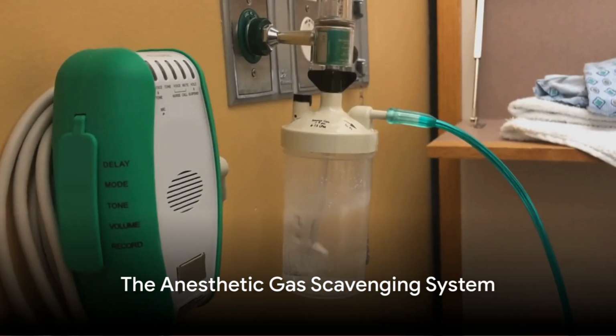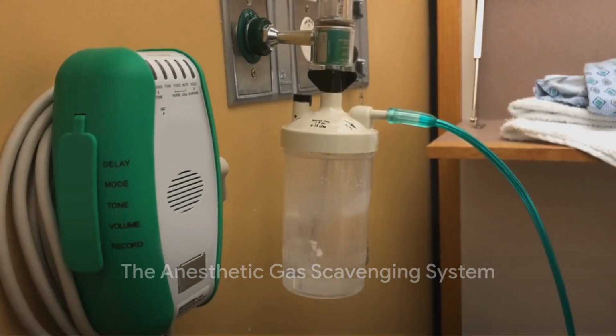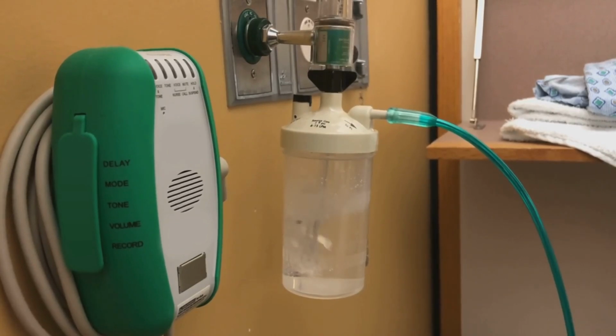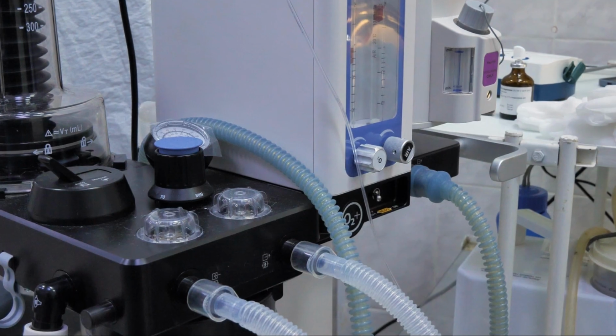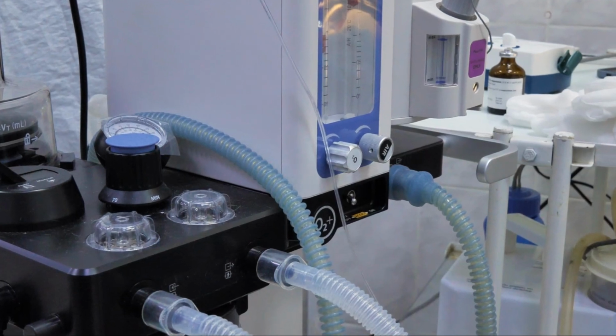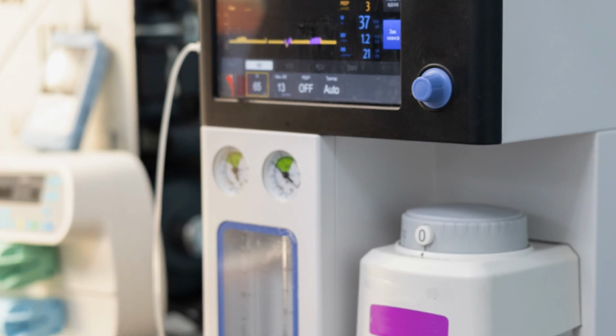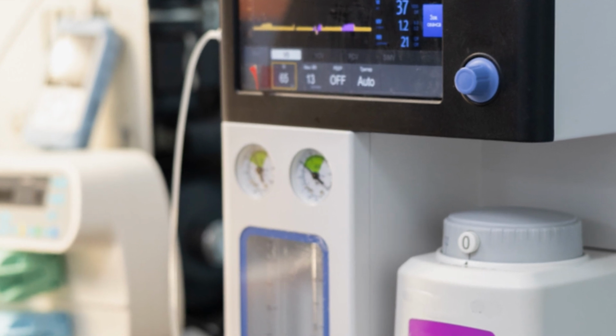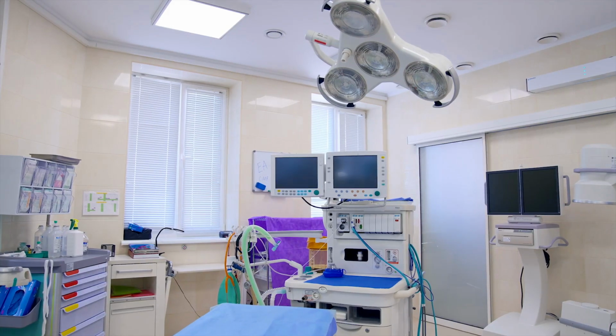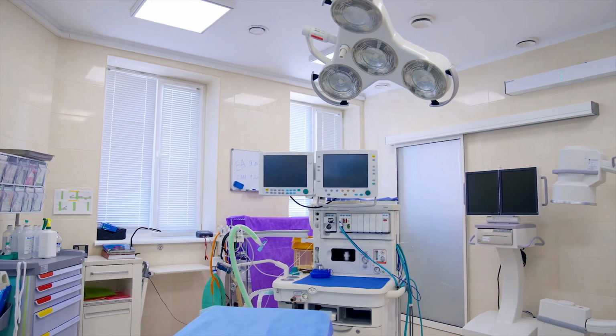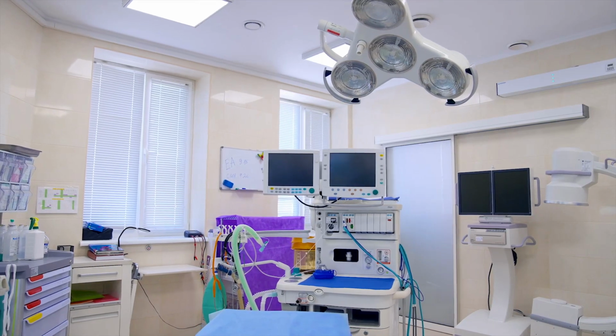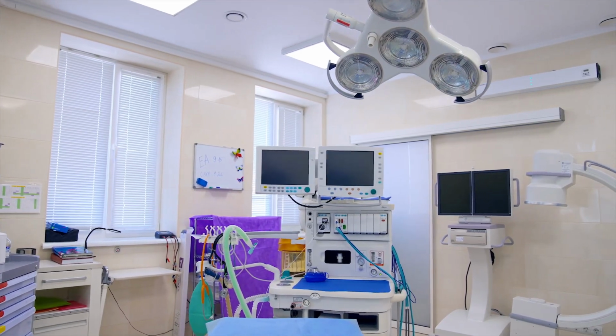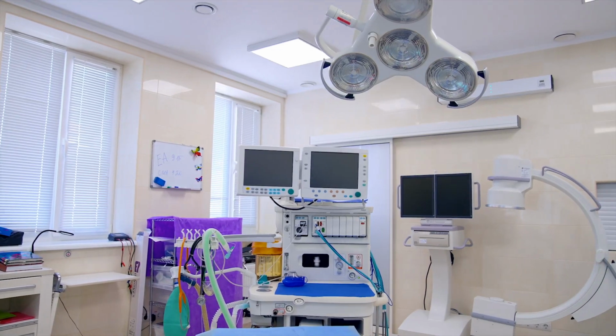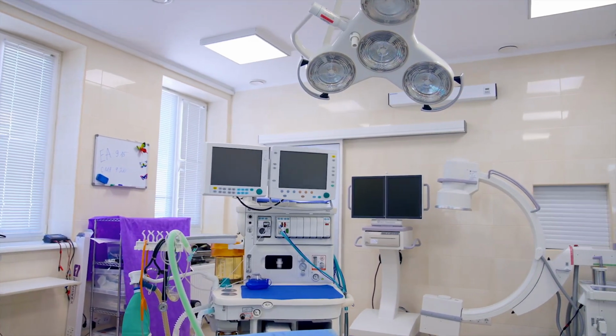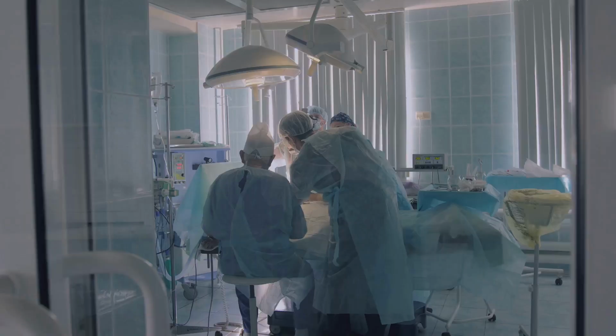Let's turn our attention to the anesthetic gas scavenging system. This part of the anesthesia machine plays a pivotal role in maintaining a safe and healthy operating room environment. But how exactly does it do this? Well, it all boils down to its primary function: to remove excess anesthetic gases from the operating room. You see, during the anesthesia process, it's inevitable that some anesthetic gases escape from the patient's breathing system. These gases, if left unchecked, can build up in the operating room air, posing a potential health risk to the healthcare team and even the patient.